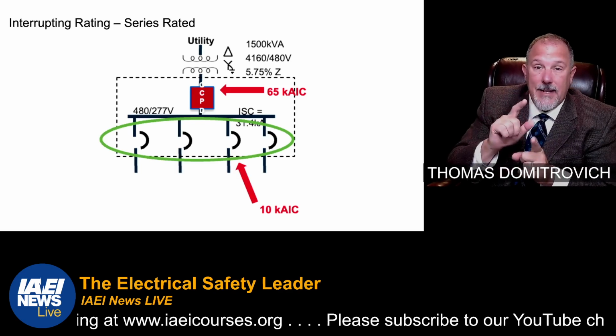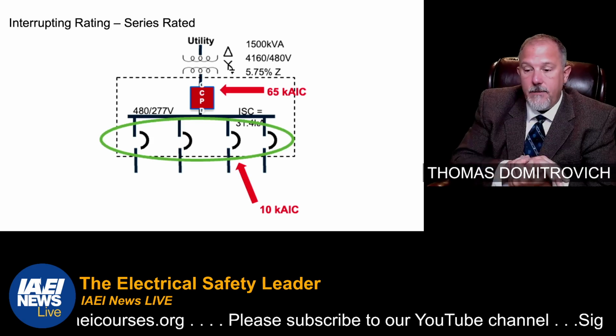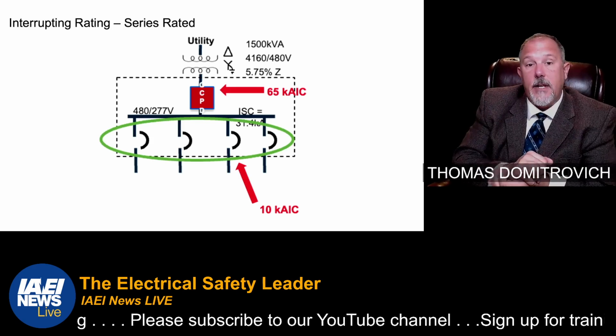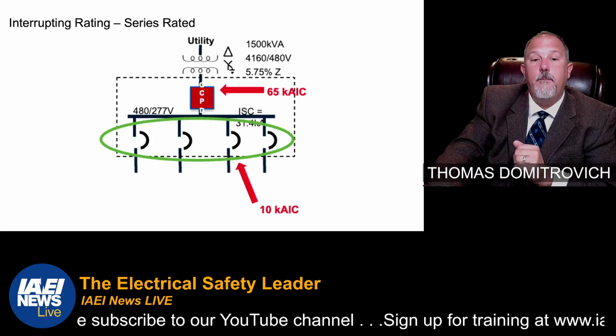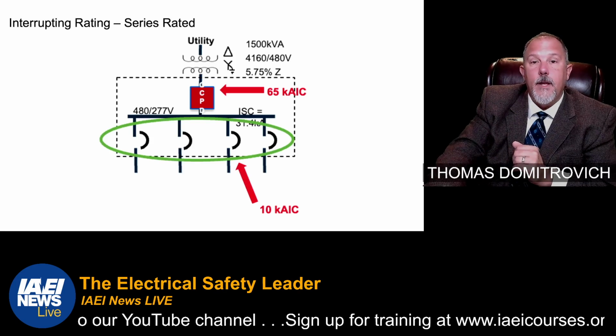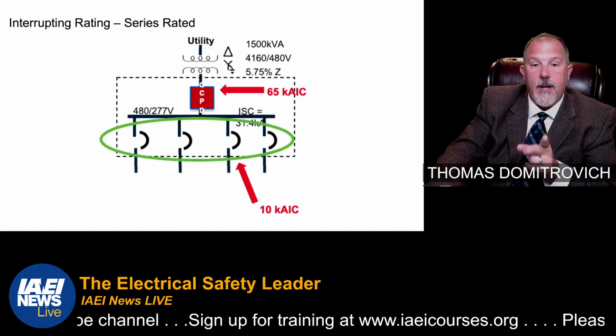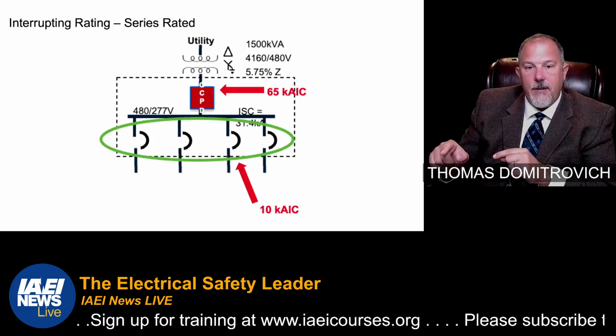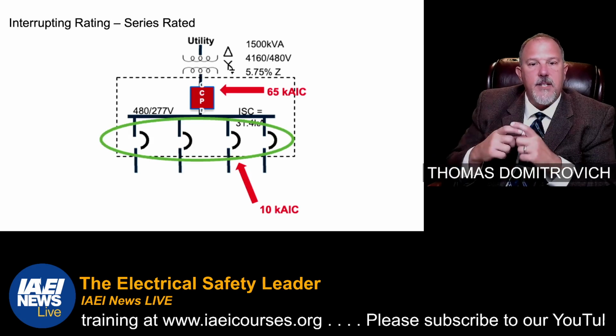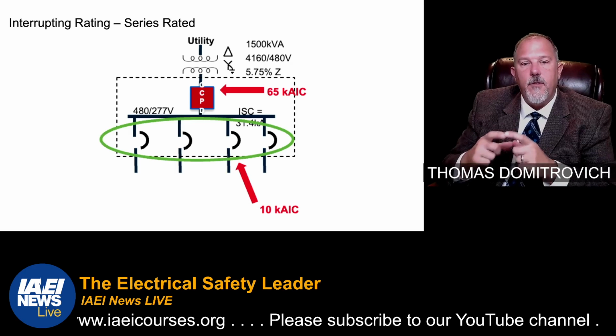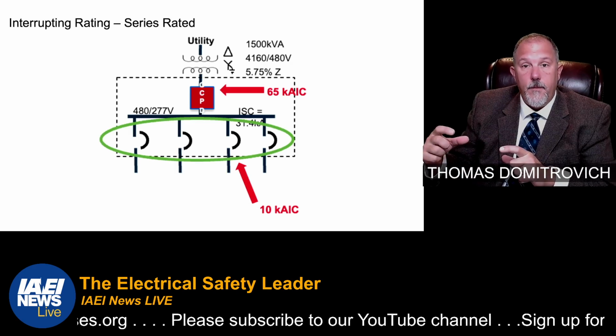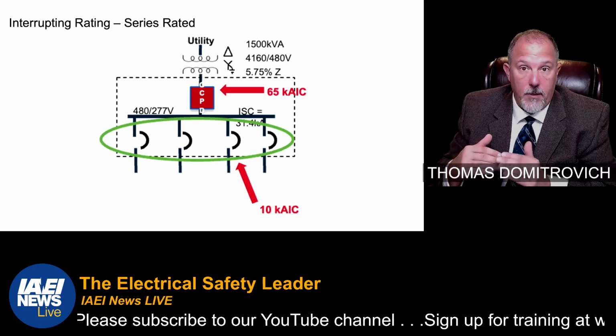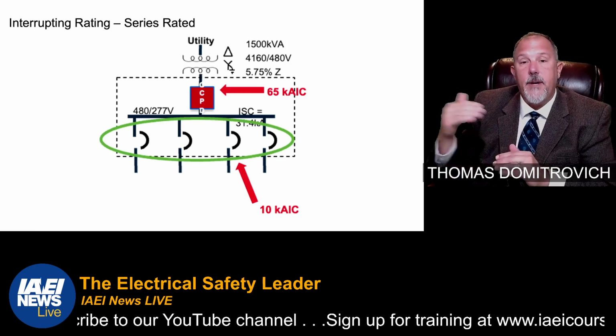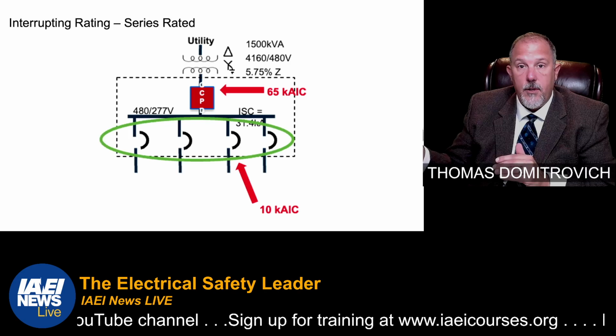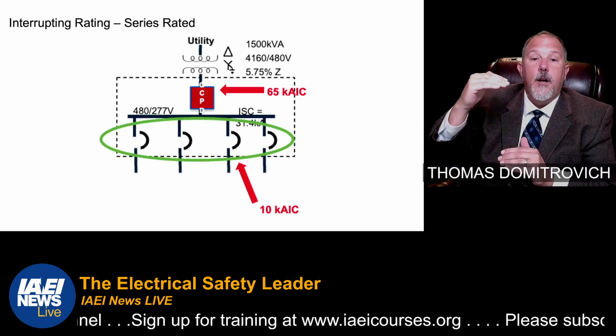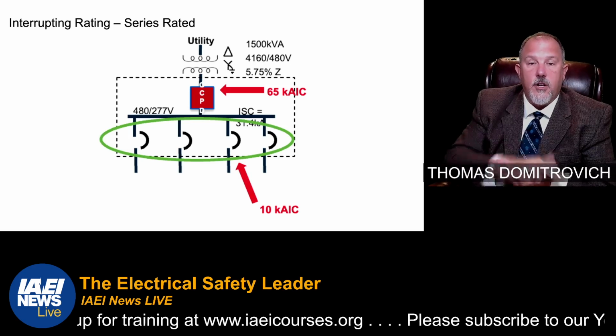240.86. 240.86 is another one for you to remember, and go check it out because a lot of people miss the details in 240.86. These pairs of breakers have to be able to handle the available fault current at that bus. Now, you'll notice I have breakers downstream and I have a square box upstream. Why do I do that? Because the upstream overcurrent device can be a circuit breaker or a fuse. The downstream device will always be a circuit breaker.